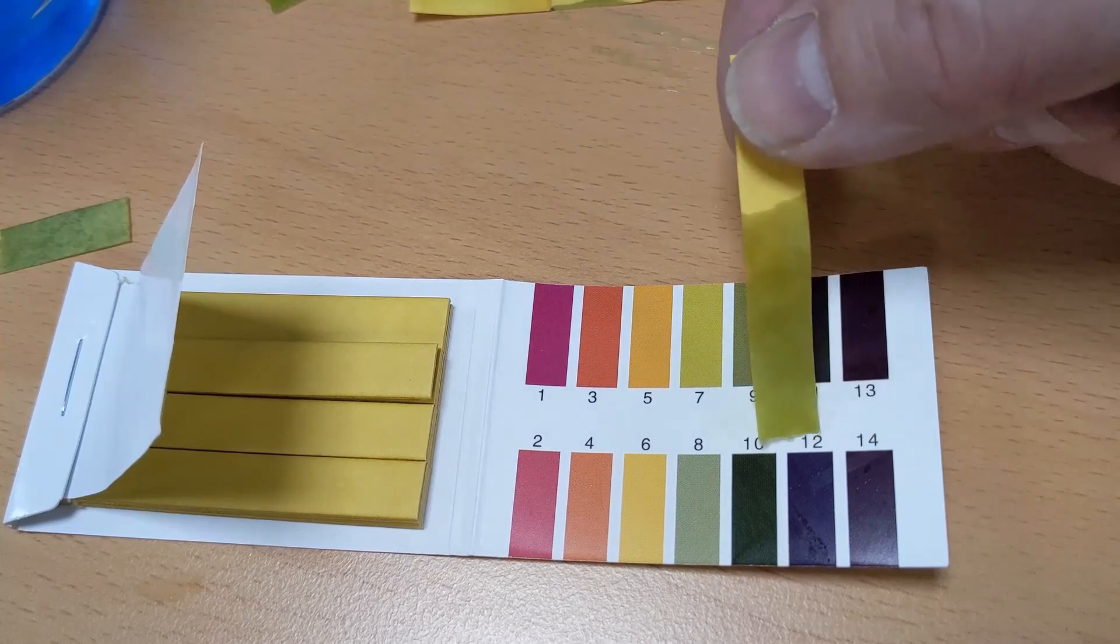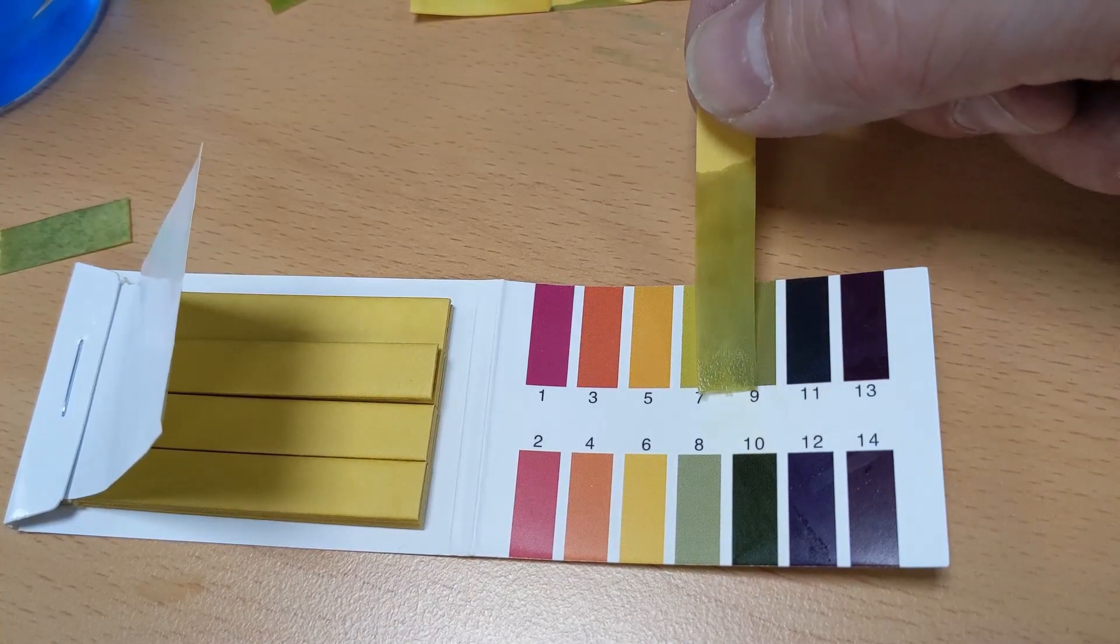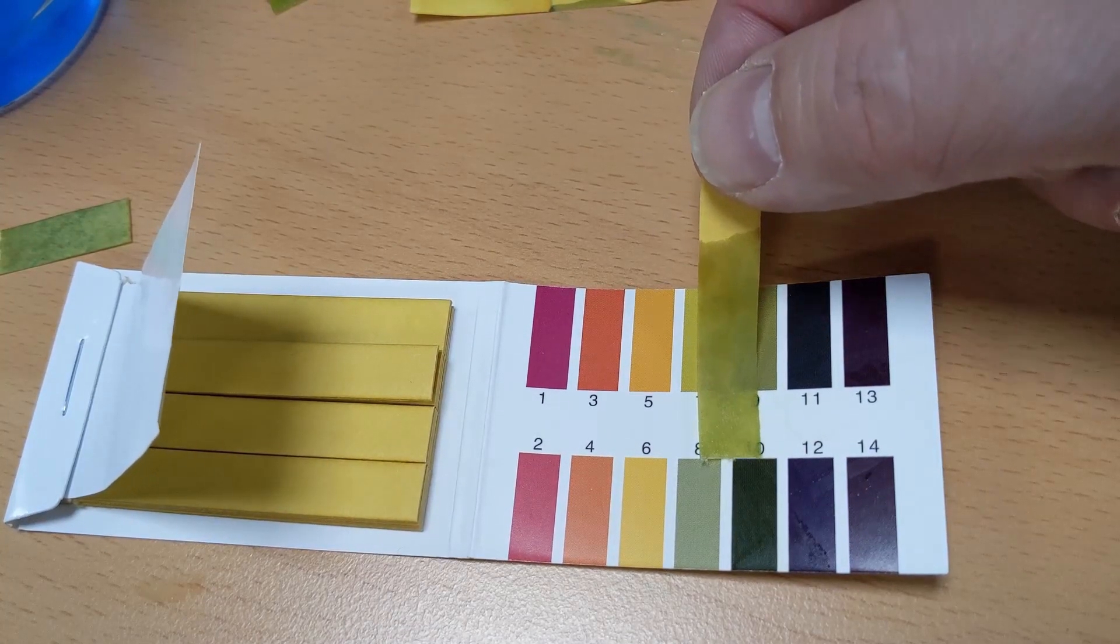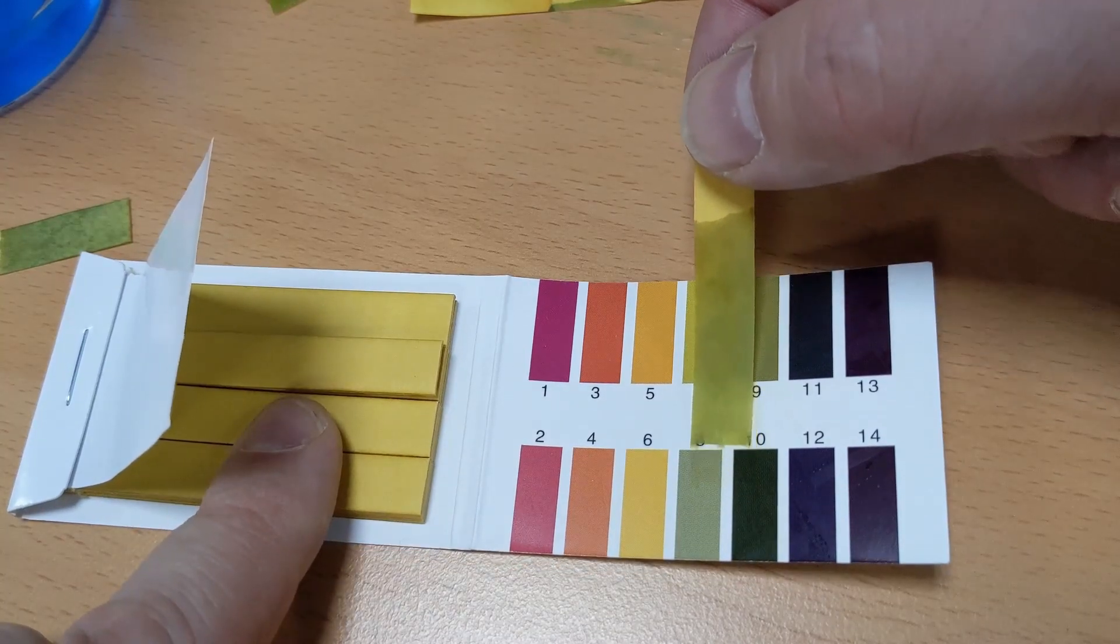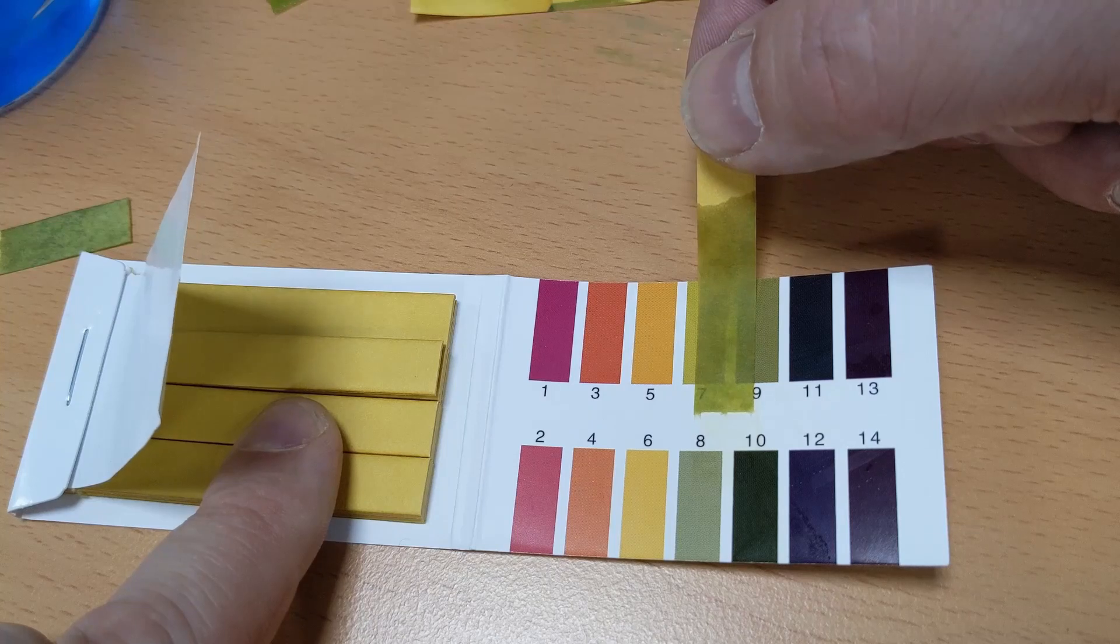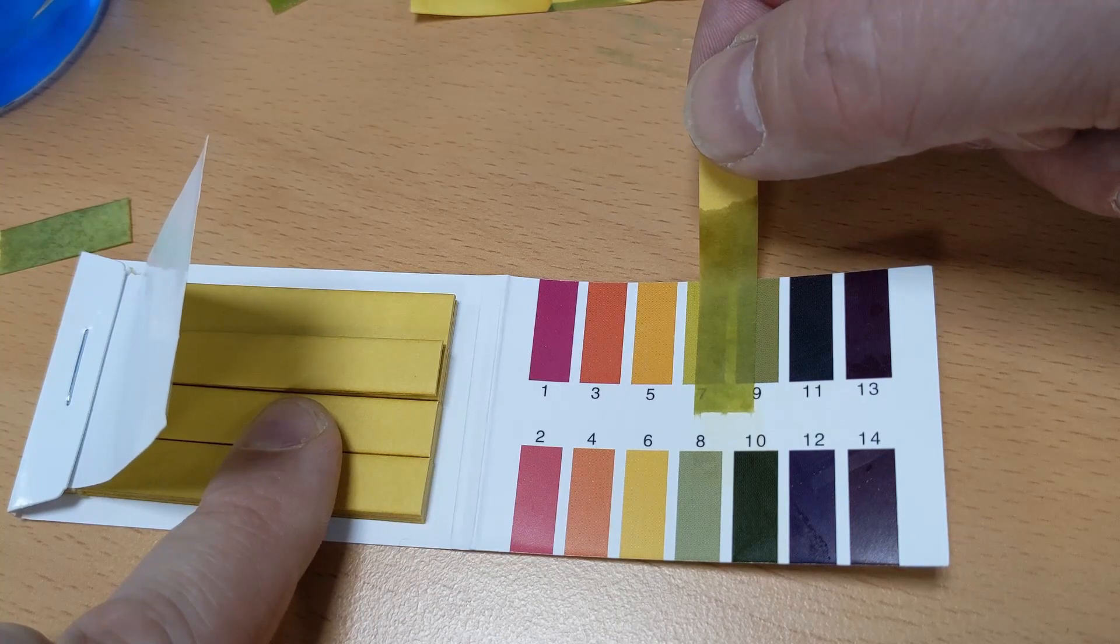We can also measure the pH level of that water, just giving us a good insight as to the water quality level. So we've got an idea what it looks like, we've got the glycol level, and we've also got an idea of the pH level. This gives us a nice overall insight into the water quality.